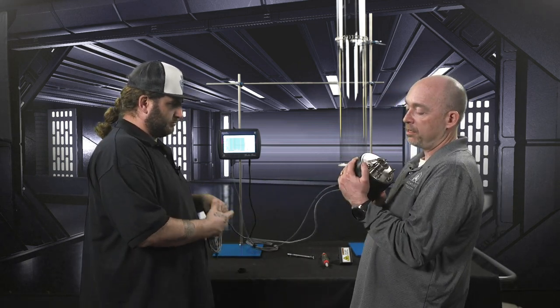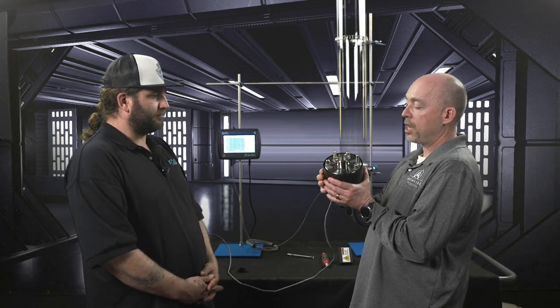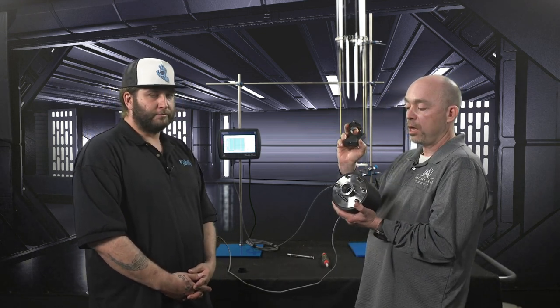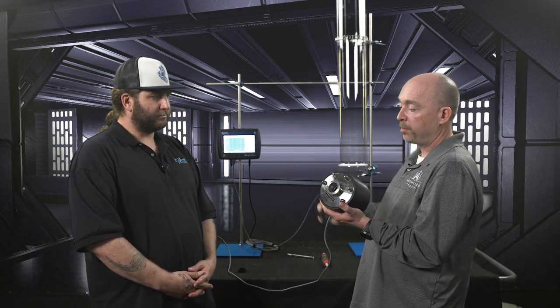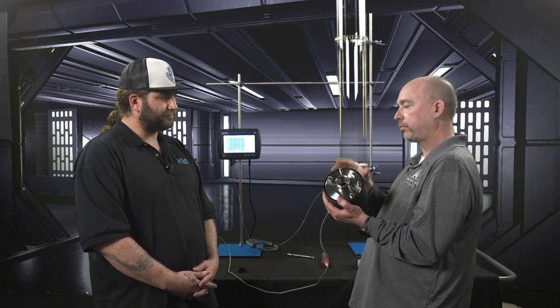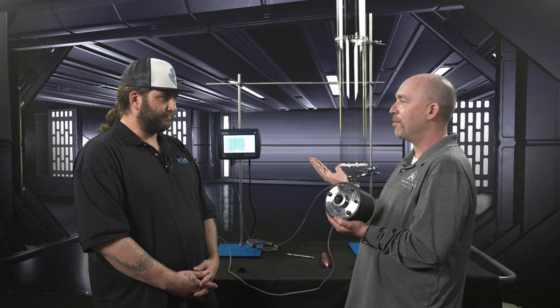This is a design number four actually. So first we created a way to put our sensor in a place where we can actually see that fluid with 1.5 inch sanitary flanges that worked well. However, with cryo, things ice up.